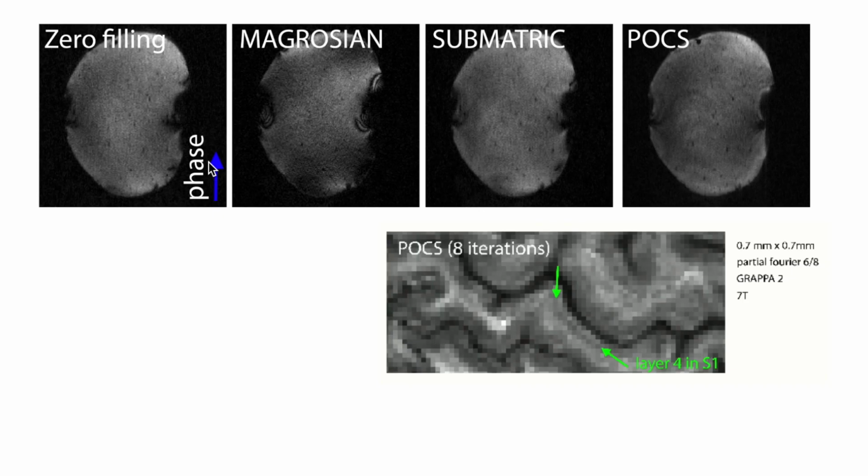And the effect on those data can be particularly well seen in this phantom here that has a lot of bubbles in there. And this also means that there are a lot of B0 inhomogeneities that partial Fourier sometimes cannot really recover and has problems with. So with zero filling, it's not really sensitive to these inhomogeneities. You don't have these ring artifacts that you have in other algorithms. However, there's a lot of smoothing in the phase encoding direction.